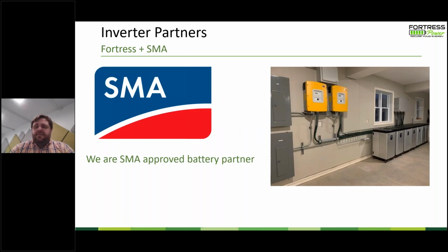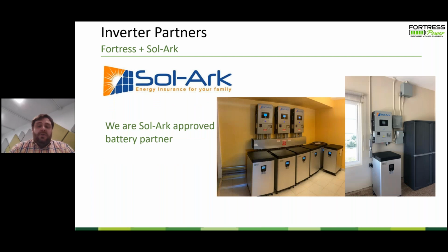Here's another configuration, a big off-grid rig with Sunny Island. The SMA also has a high voltage inverter. We do not yet have a high voltage battery. These batteries must be wired in parallel with each other. Often what that means is putting a combiner block of some sort in the gutter between the batteries and the inverters. The inverters have their own disconnects, and the batteries have their own disconnects. We just put a bus bar inside the trough and combine them together.